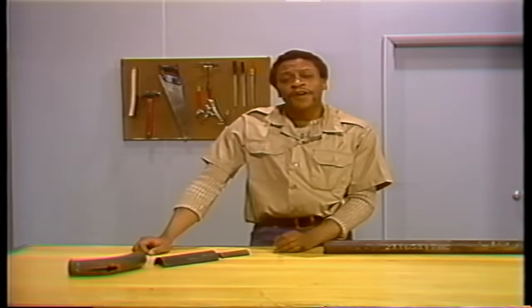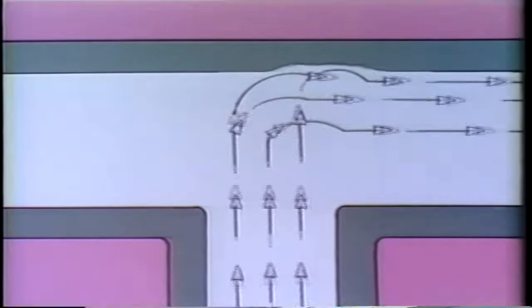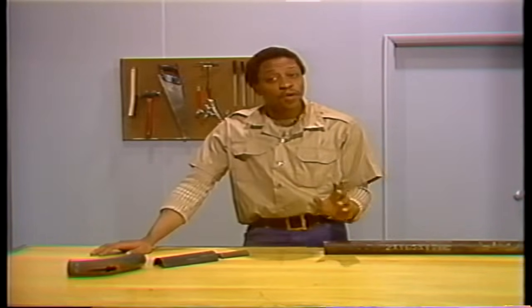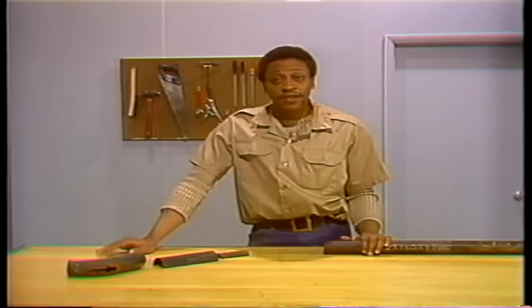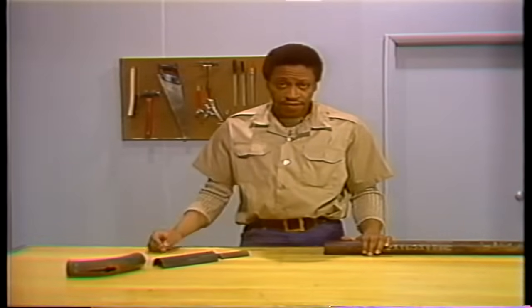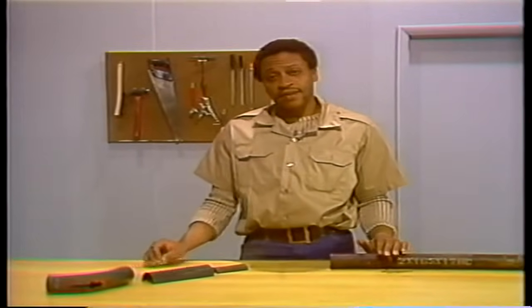The next basic cause of tube failure is erosion. Erosion is the gradual wearing away of tube metal, which weakens the tube. It can occur on either the inside or the outside of the tube. Erosion on the inside is produced by the flow of water or steam; on the outside, by the flow of gas and ash. Erosion from gas and ash can be particularly severe in coal-fired boilers because they produce large amounts of very abrasive ash. Erosion can also result from steam leaks — when steam from a leak in one tube is directed against another tube, it can erode the metal and cause a failure.